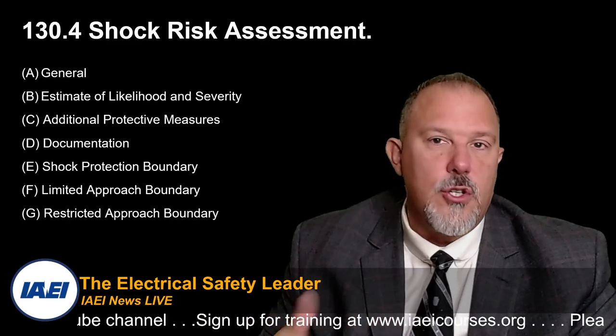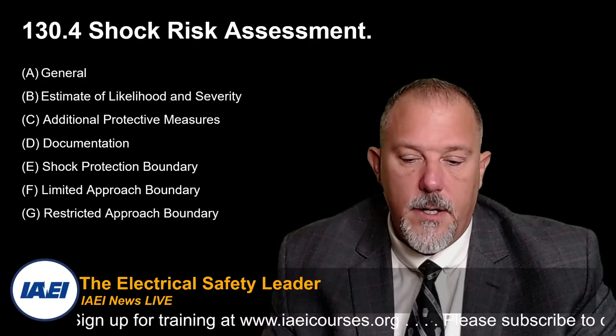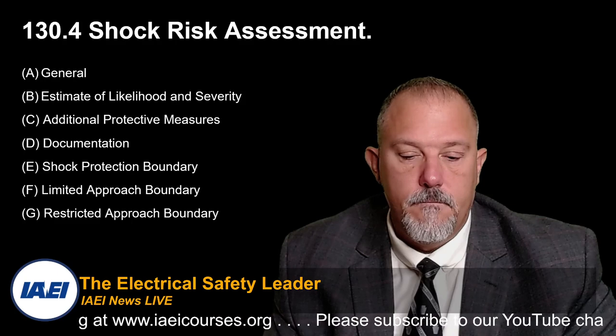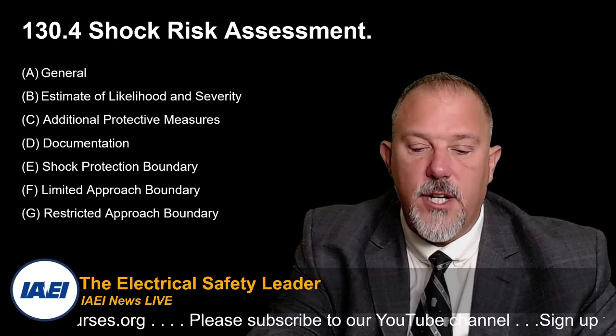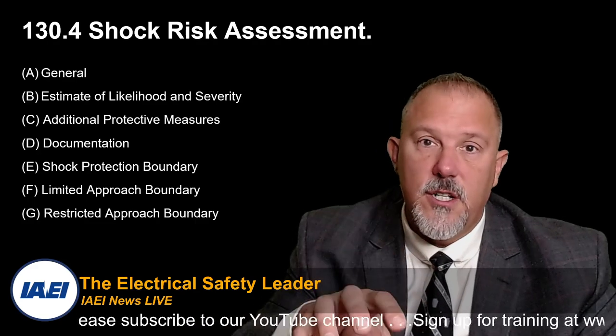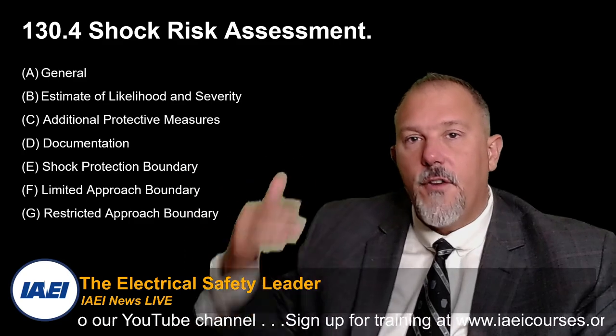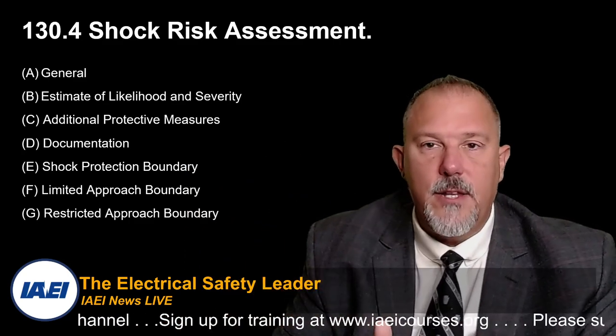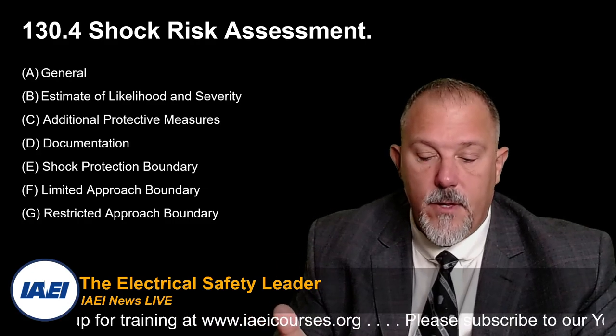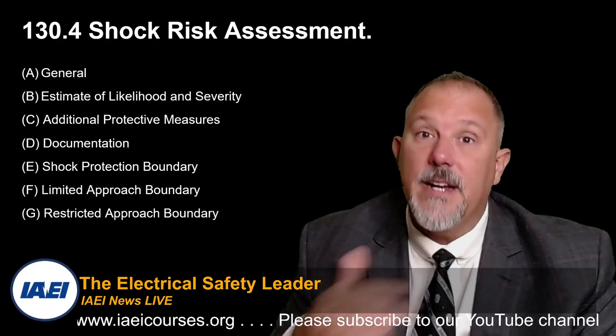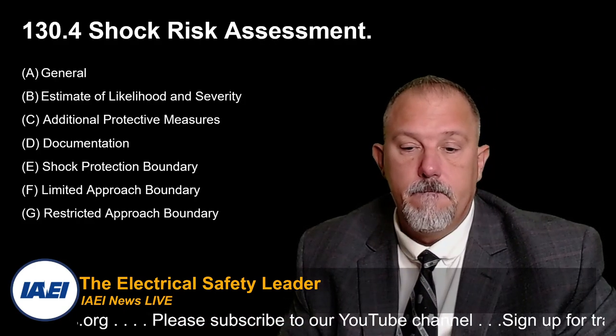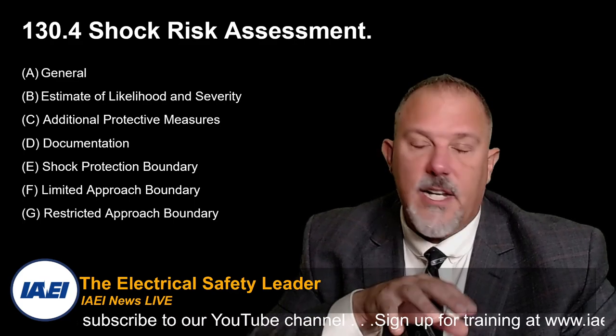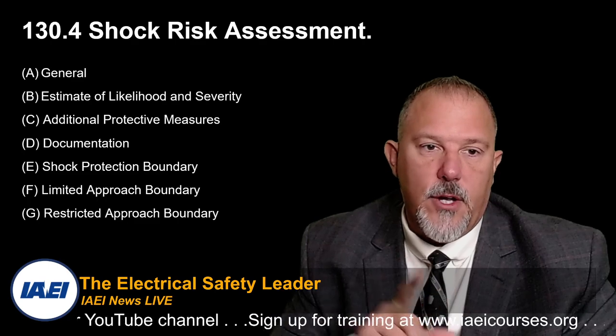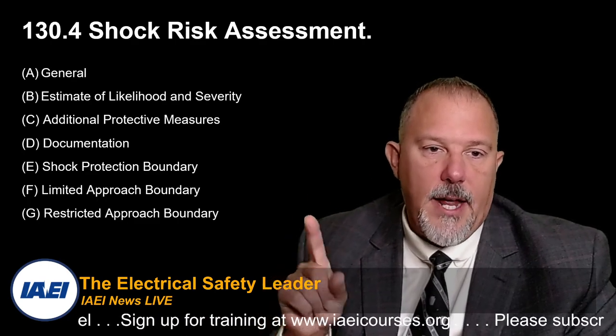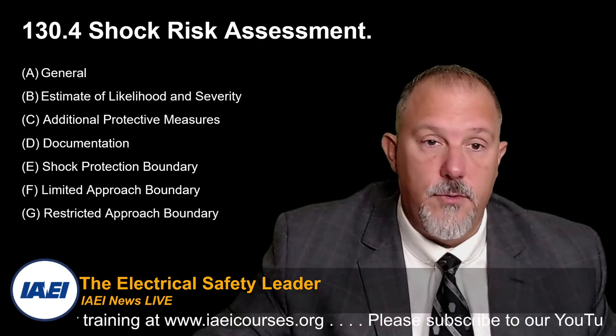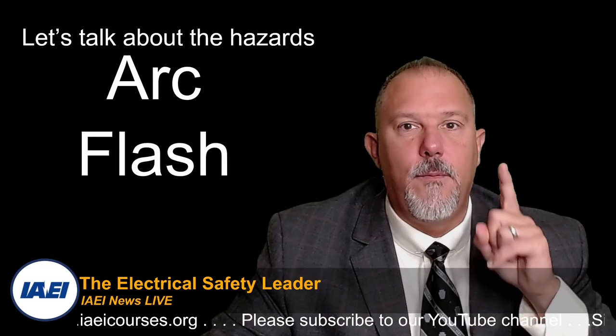The moment you enter, you can't have a tool on you that is non-insulated and conductive. The qualified person is insulated or guarded from energized electrical conductors or circuit parts. This is in the restricted approach boundary. This is the smaller. So you have a further number, which is your 3 foot 6. And then once you get into, say, 1 foot for 480 volts, 2 foot 2 inches for 4160, now you've got other special conditions you need to consider. And it's all in section 130.4, shock risk assessment. We go over the boundaries. We have the shock protection boundary, we have the limited and the restricted approach boundaries. Understand those. But again, you've got to be able to recognize the hazard.